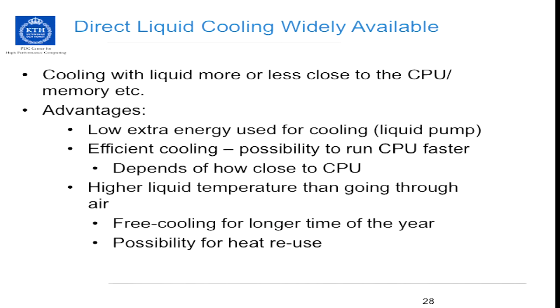We talked a bit about PUE before, and I'd say today PUE has sort of lost some of its value. Many of the new computer halls are really good - you have a PUE of 1.1, 1.2, or 1.3, and it doesn't matter so much anymore. I'd say heat reuse gives much bigger savings than trying to improve the PUE further. In fact, we haven't even calculated the PUE on our computer center. People are shocked by that, but it's much more interesting to see how economical heat reuse is and how it contributes to a good environment.